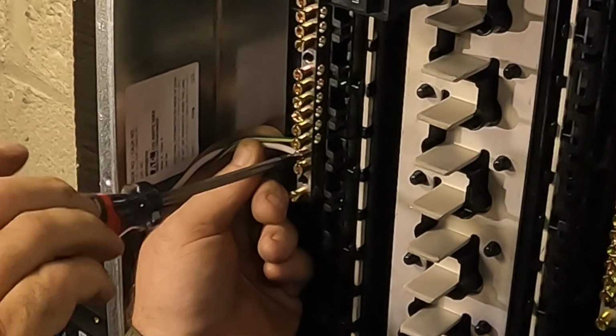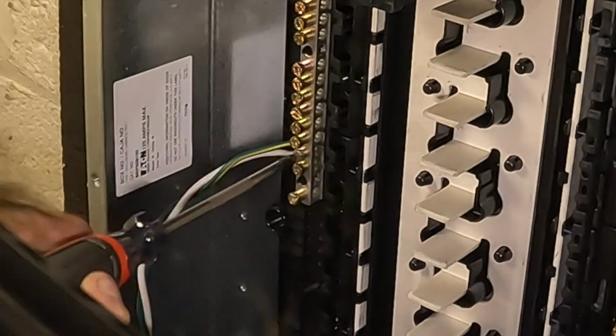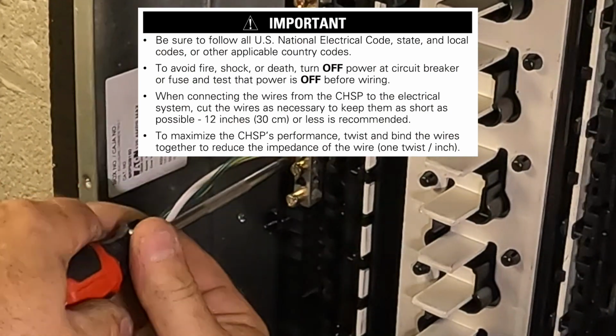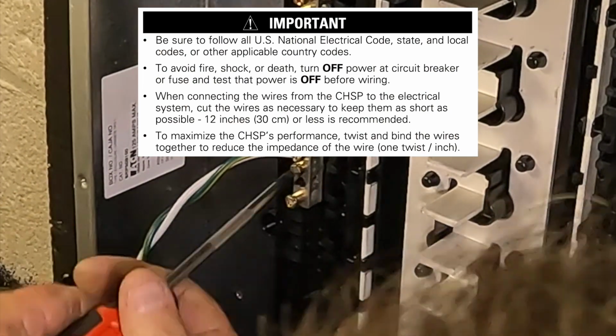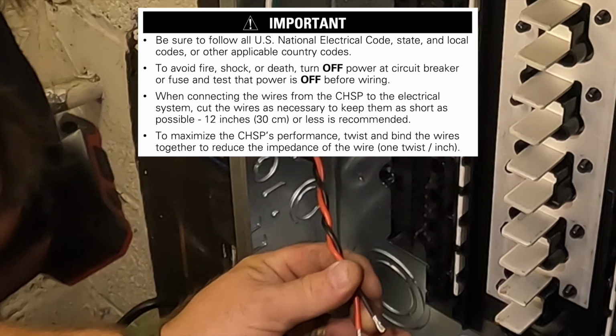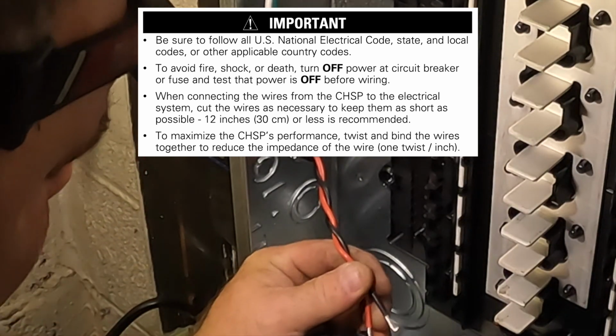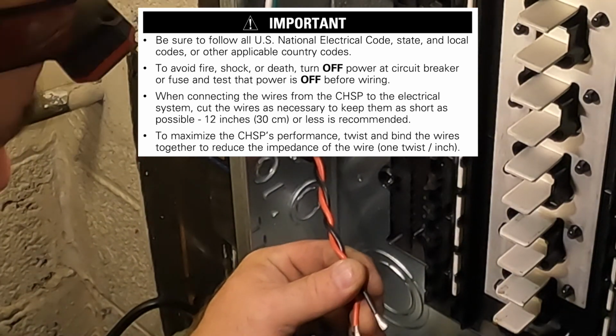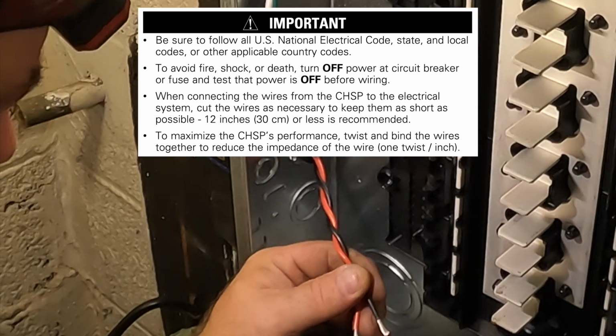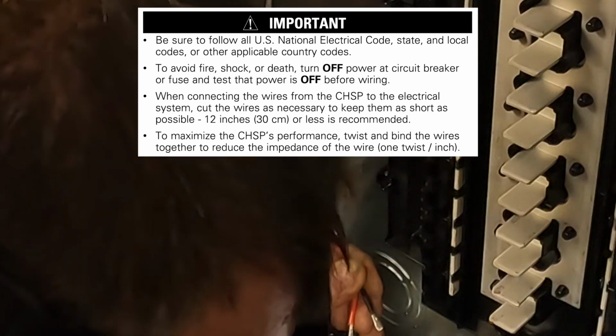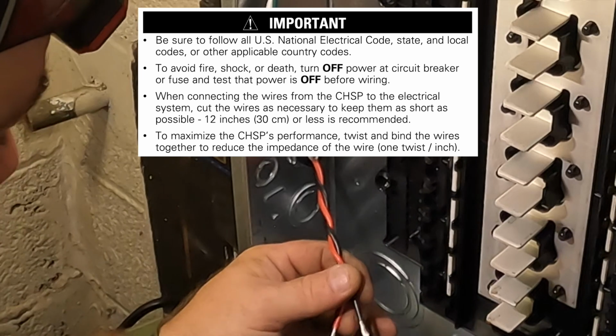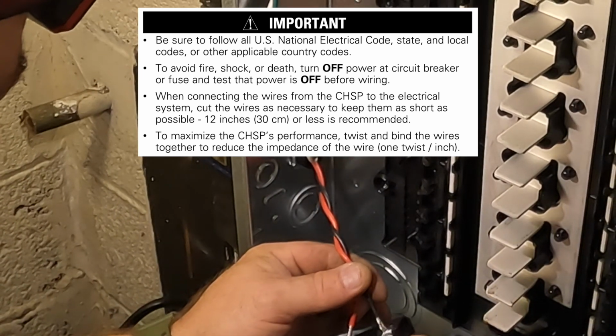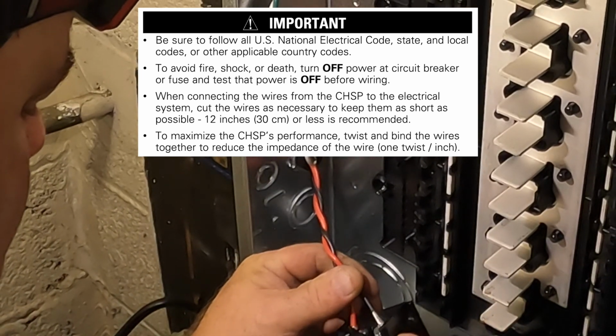These are the directions that come with the whole house surge protection device by Cutler-Hammer that you see me installing in this video. And I wanted to emphasize 2 of the 4 bullet points we see here. The third one says, when connecting the wires from the Cutler-Hammer surge protection device to the electrical system, cut the wires as necessary to keep them as short as possible. 12 inches or less is recommended.